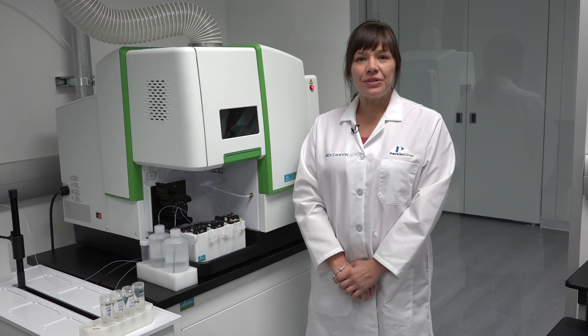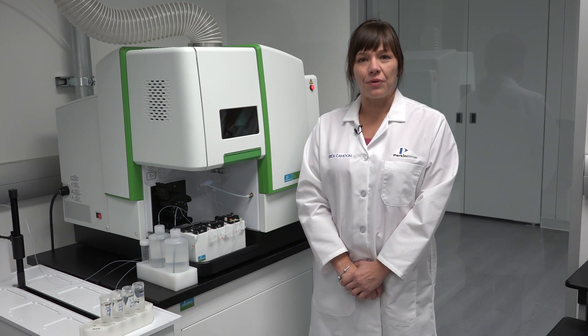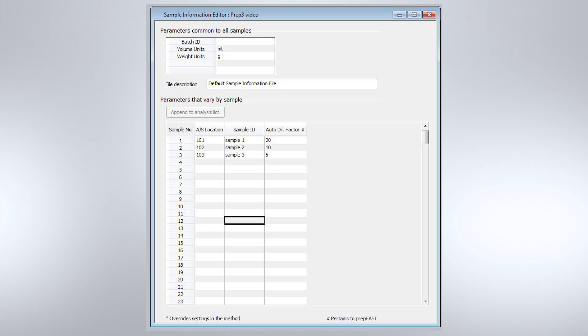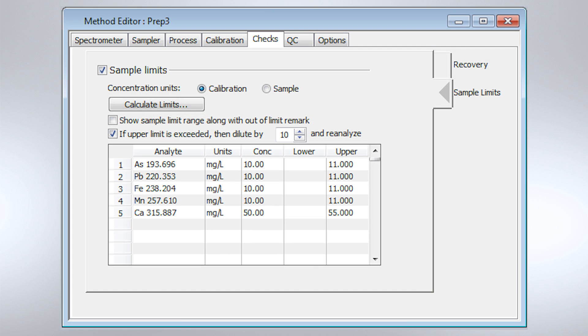There are two different options for auto dilutions of overrange samples. If you know prior to analysis that the sample is overrange, you can set a predefined dilution of that sample. If you are unsure of the concentration ranges of your samples, in the software you can list the acceptable concentration ranges. These are analyte-specific for your samples, and if any sample concentration falls above this range, the PrEP3 will dilute by the dilution factor predetermined by you in the software.